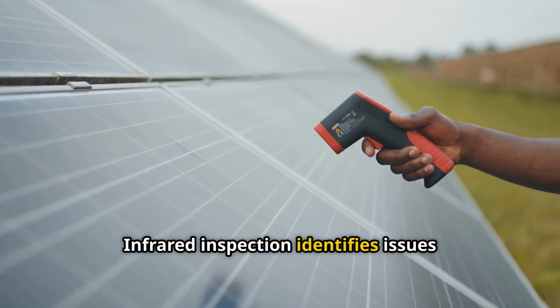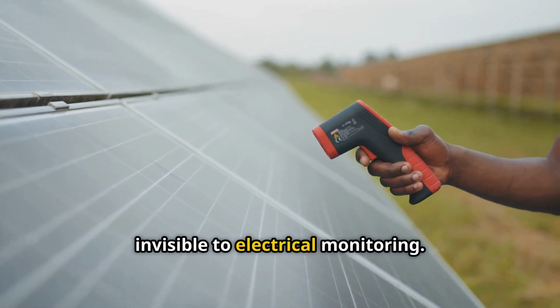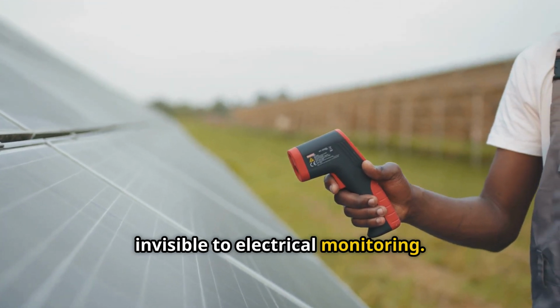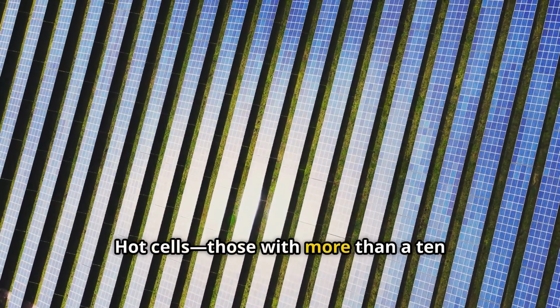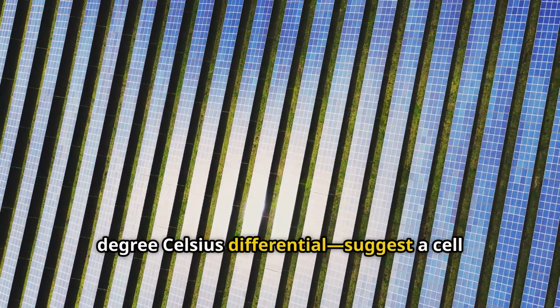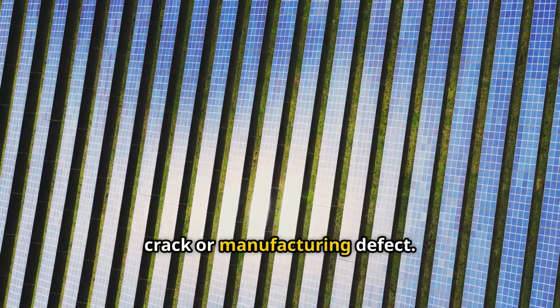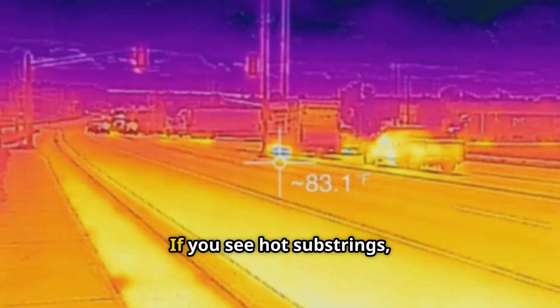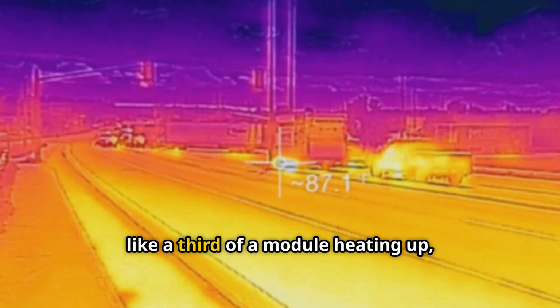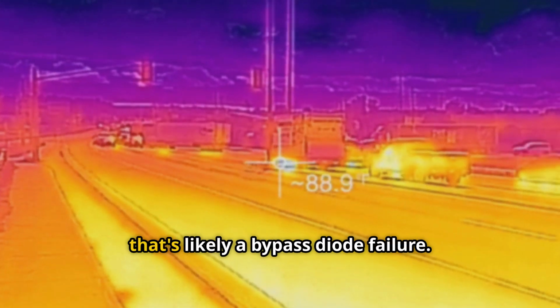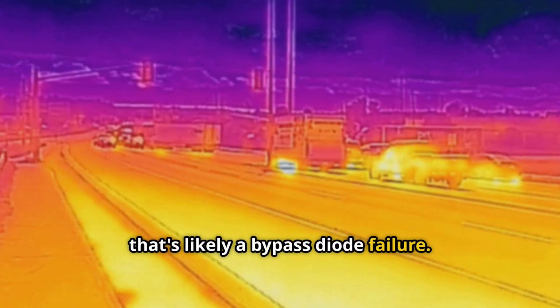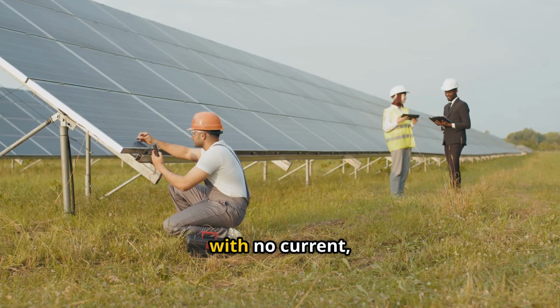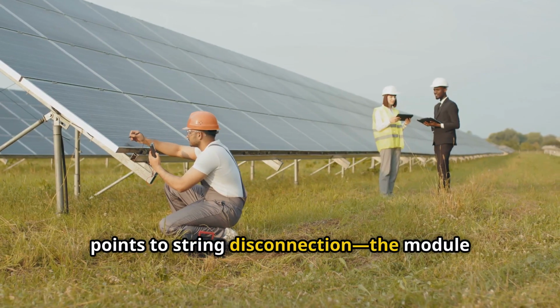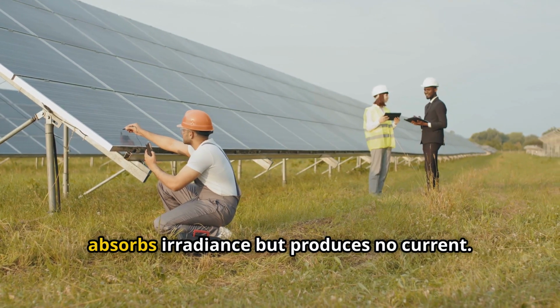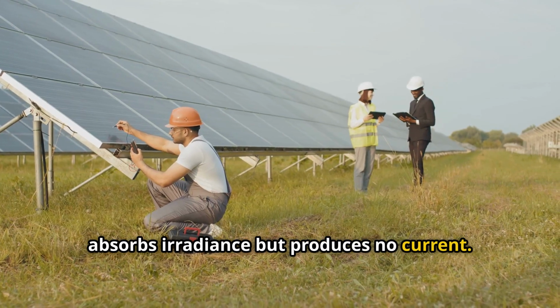Infrared inspection identifies issues invisible to electrical monitoring. Hot cells, those with more than a 10 °C differential, suggest a cell crack or manufacturing defect. If you see hot substrings, like a third of a module heating up, that's likely a bypass diode failure. Full module heating, with no current, points to string disconnection. The module absorbs irradiance but produces no current.